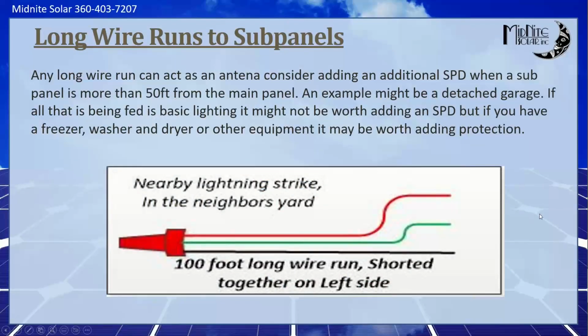So we talked about long wire runs, and here's my image. I probably should have had it up further. This is something I've always wanted to try, but I've never had the braveness to actually sit out there during a lightning storm with my meters and try this. But a long wire, if you could picture this wire with all 3 conductors twisted together, you would think, okay, it's always going to be 0 volts at the other end. But because of the resistance and voltage drop in the wire, during a nearby lightning strike, it can be thousands of volts induced into that wire, and the resistance allows there to be a pretty high potential on the other end. So that's just something to keep aware of.